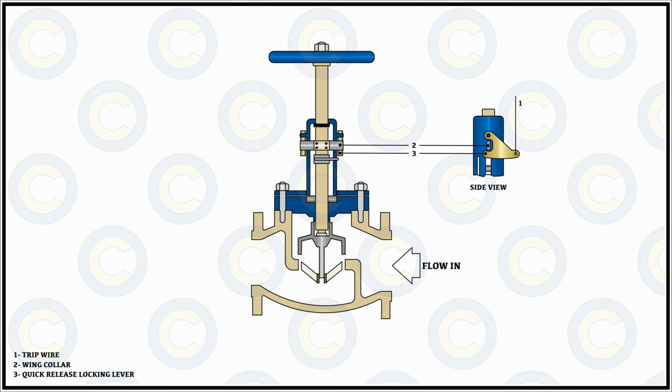So now imagine that your valve is in a situation where it is fully open. Then at the pivot part, there is a disc-like structure which protrudes outside, or a needle-like structure which protrudes outside, and this particular part, in the open condition, is being held by a latch. So now basically this particular disc that we are looking at is being held open by a latch. That is basically how in a quick closing valve we are keeping it open, that is through manual action. We have opened the disc, the spindle has moved up, and this particular disc is being held open by the latch.